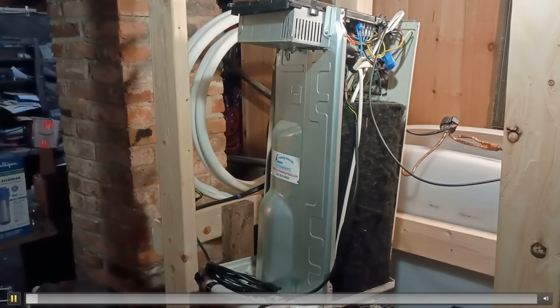So the one issue that remains is that the heat pump occasionally reverses direction. This is to blow out leaves or something that's accumulating onto the outdoor unit, assuming it were outdoor. The problem is that when that reverses, this pump, I think it's cavitating. It's trying to suck water back through all the lines that are outside, and it doesn't want to do that. So I haven't actually resolved this issue yet. I have some ideas, but if you have any ideas on how to get around this, that would be great. Greatly appreciate it.